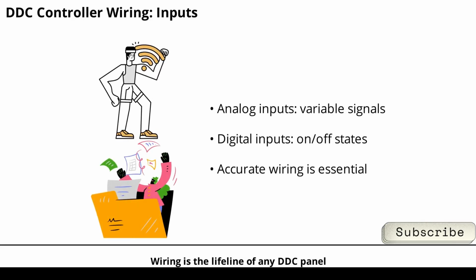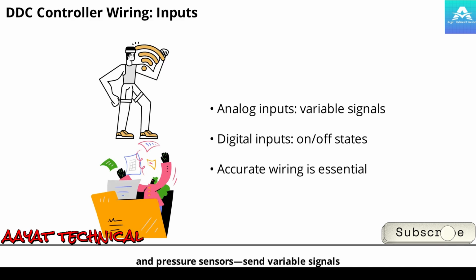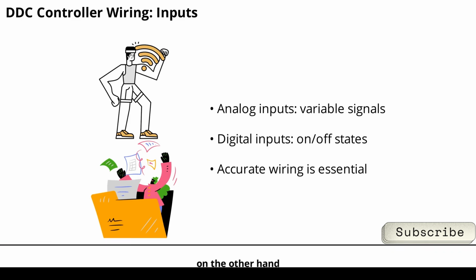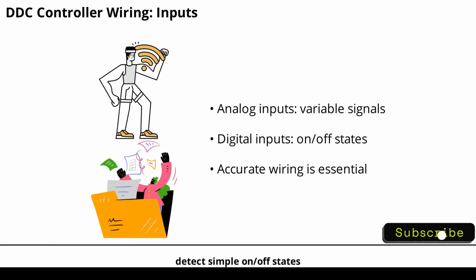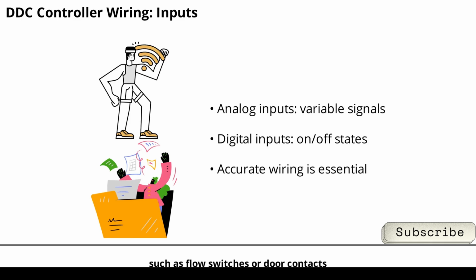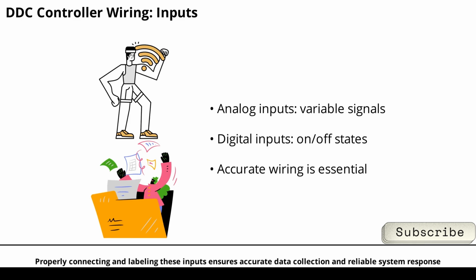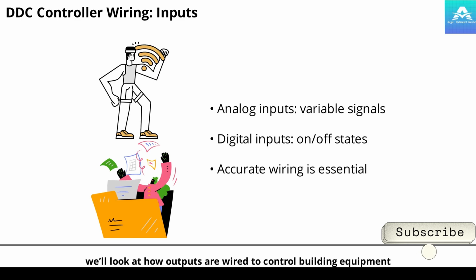Wiring is the lifeline of any DDC panel. Let's start with inputs. Analog inputs like temperature, humidity, and pressure sensors send variable signals, typically 0-10V or 4-20mA, to the controller. Digital inputs, on the other hand, detect simple on/off states, such as flow switches or door contacts. Properly connecting and labeling these inputs ensures accurate data collection and reliable system response. In the next scene, we'll look at how outputs are wired to control building equipment.